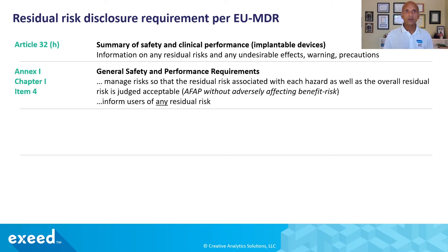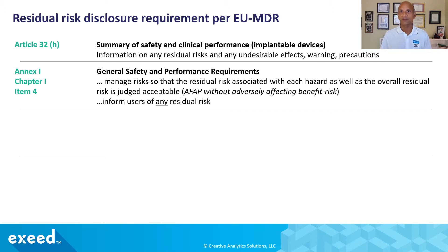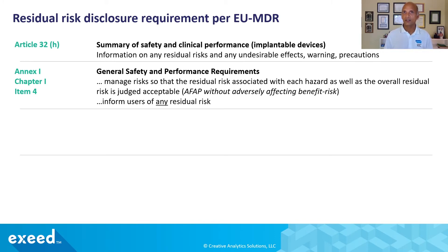In Annex 1, Chapter 1, item 4 — the general safety and performance requirements — they require you to manage risks so that the residual risks associated with each hazard as well as the overall residual risk is judged acceptable, as far as possible without adversely affecting benefit-risk. And they say to inform users of any residual risk — not just the significant residual risks, but any.